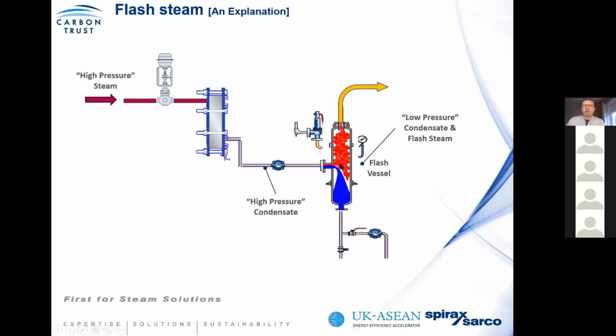the residual condensate will want to try and give up its excess capacity above that which you can hold at 0 bar. And if you can remember, we talked about the enthalpies of water in our steam fundamentals, and the higher the pressure, the higher the enthalpy of water. Conversely, what it means is that if you reduce pressure, then that condensate cannot hold on to that energy due to the thermodynamic laws and will release this energy as what we call flash steam. So in this scenario, you will generate flash steam and you'll generate low pressure condensate.